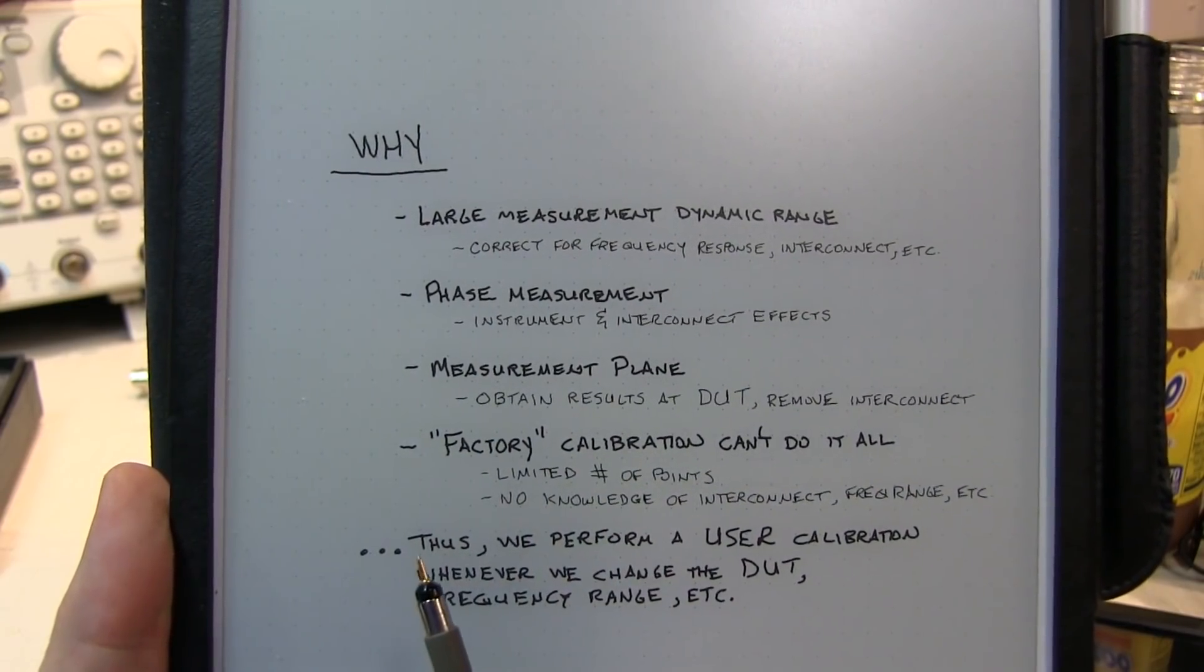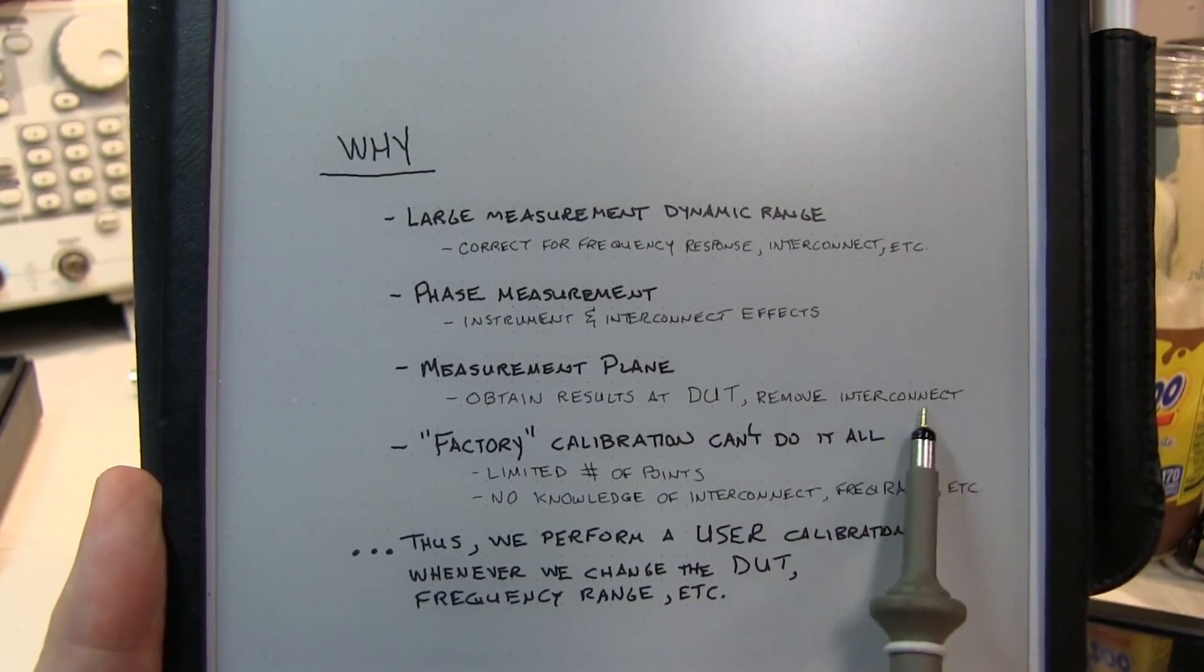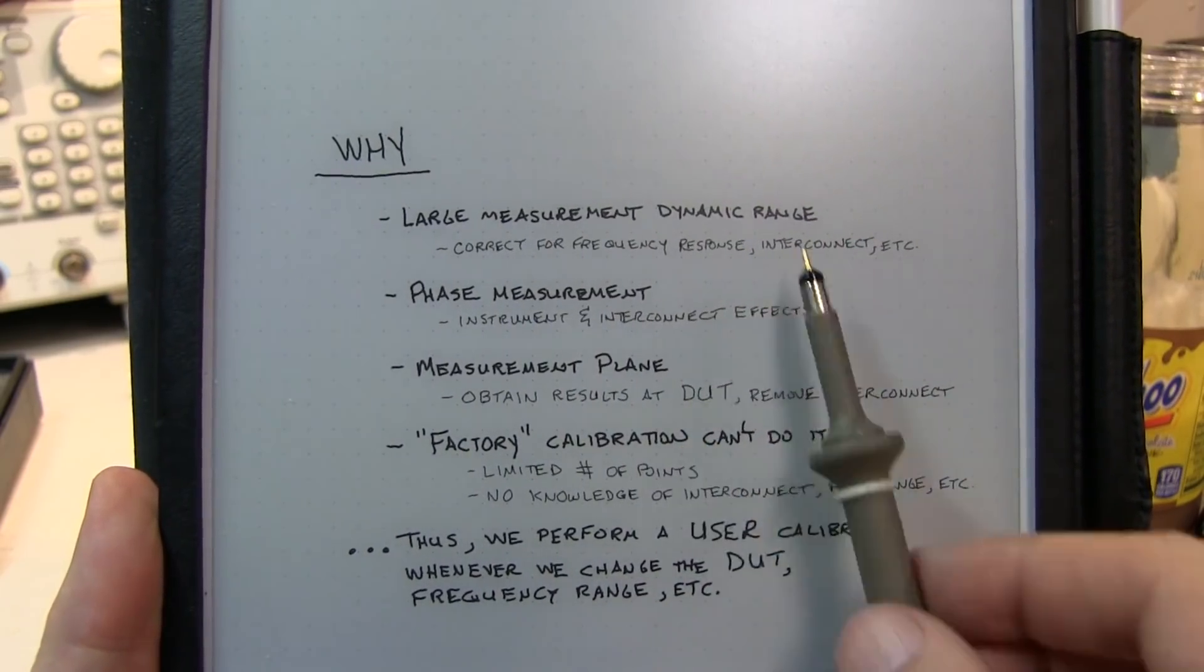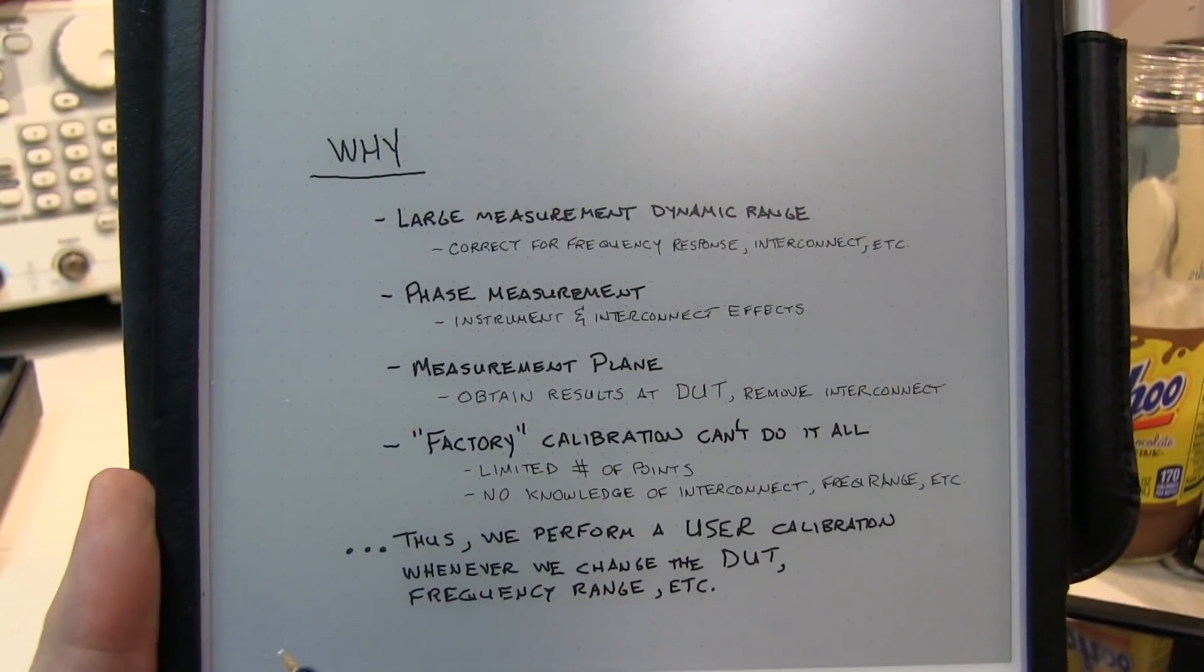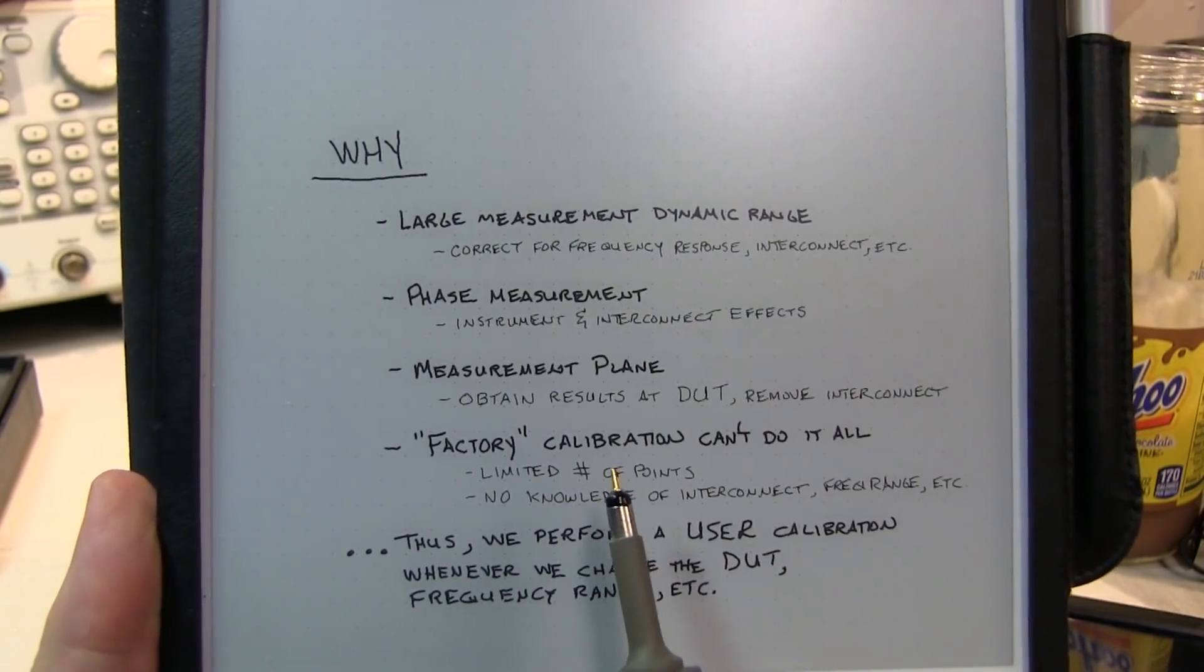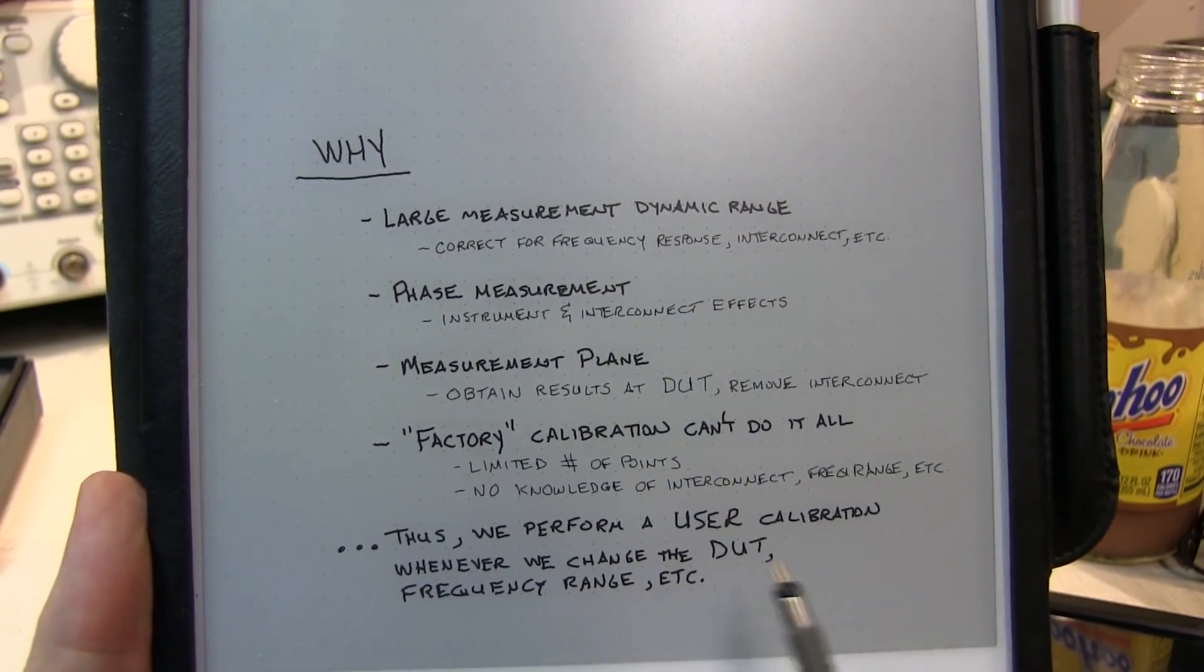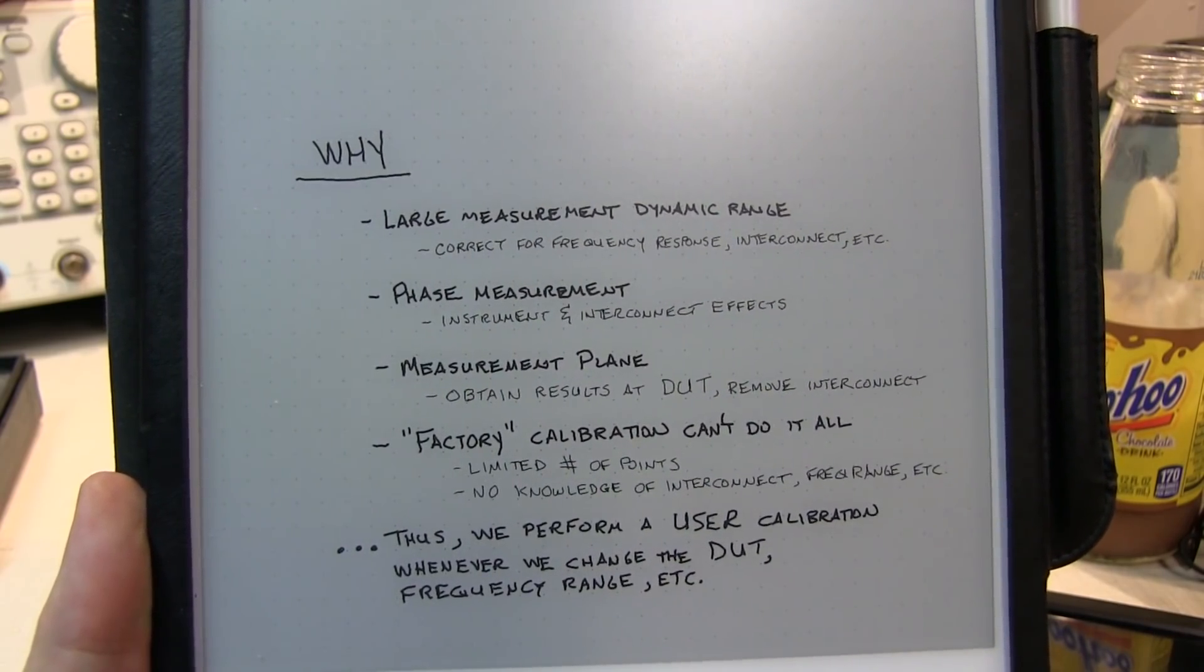So you might say, why doesn't a factory calibration do what you need? Well, it really can't. The factory's got no knowledge of the interconnect you're going to put between the VNA and your DUT, so it can't establish a measurement plane at your DUT. And it won't be able to correct for the frequency response or phase response of that interconnect. Also there's a limited number of points that a factory calibration can do, so those points most likely will not line up with the measurement points you're going to make for your DUT. Thus, we must perform a user calibration whenever we change the device under test, the frequency range, the interconnects, or anything like that.